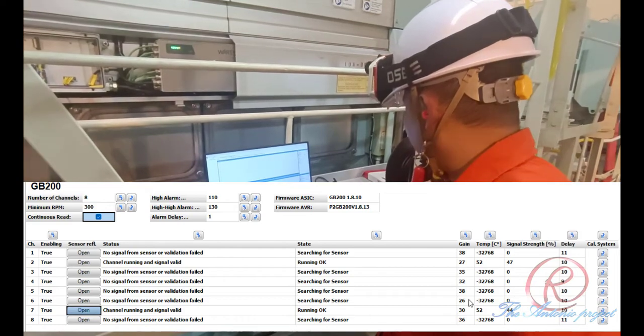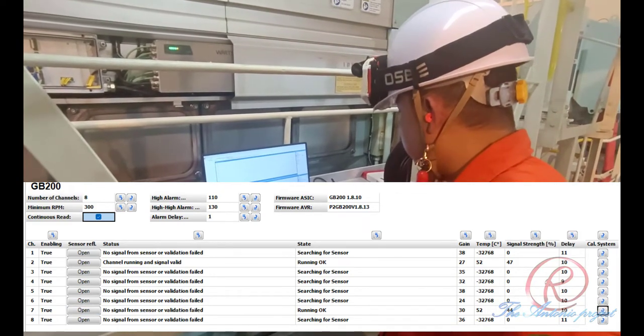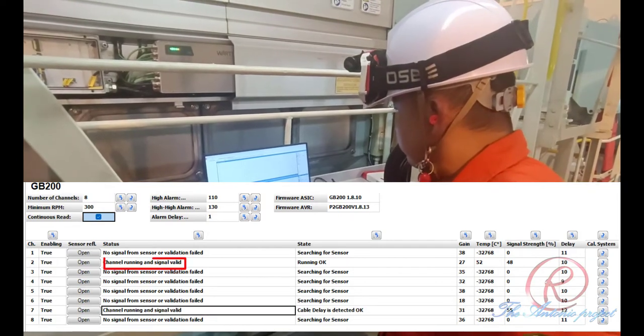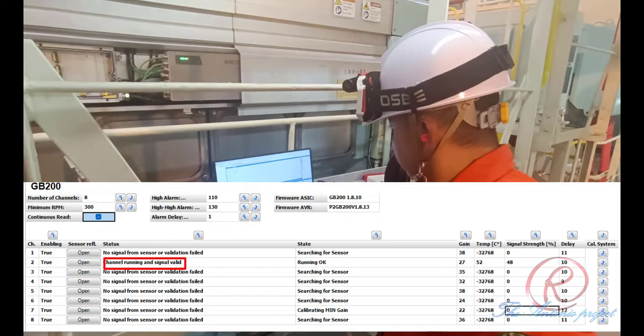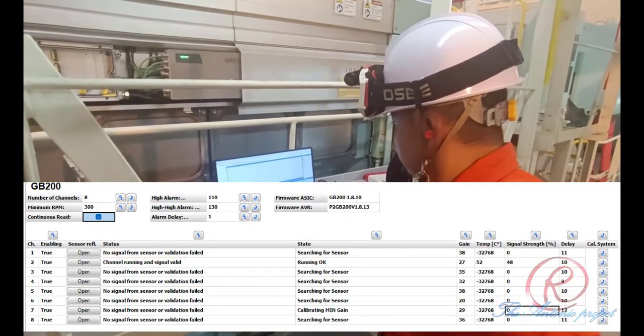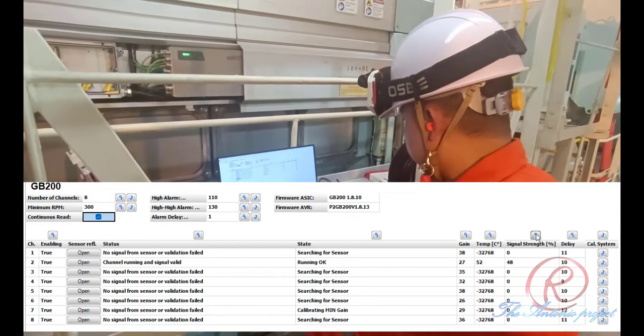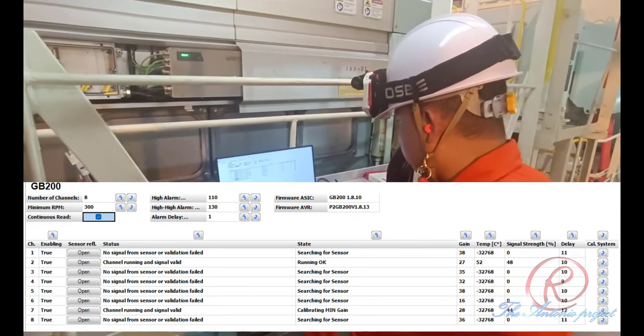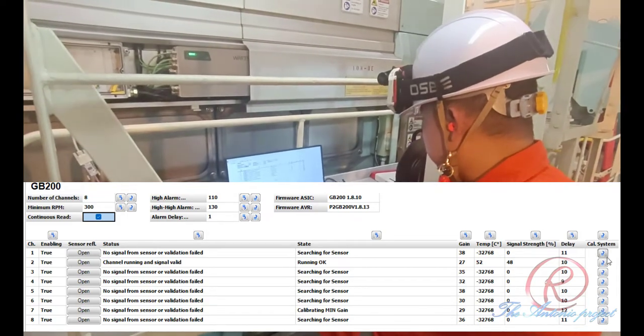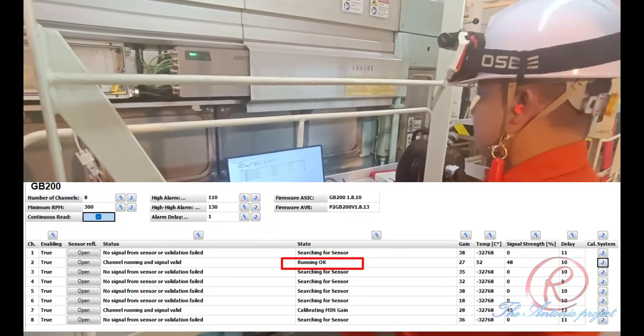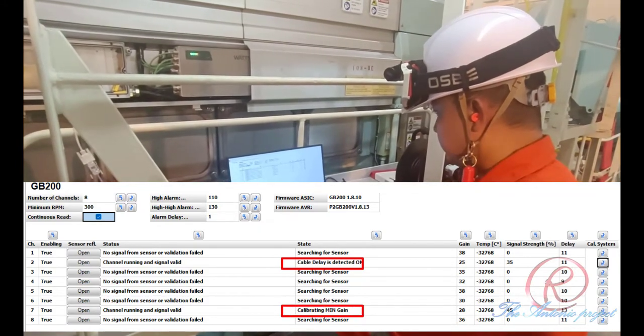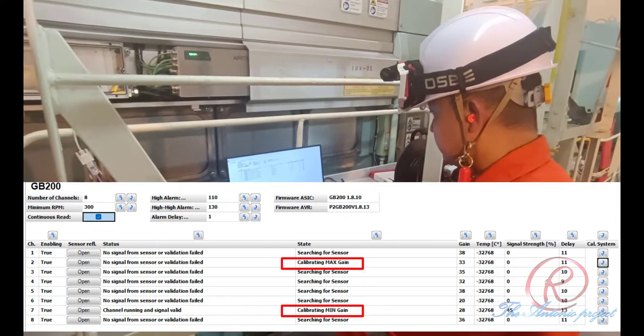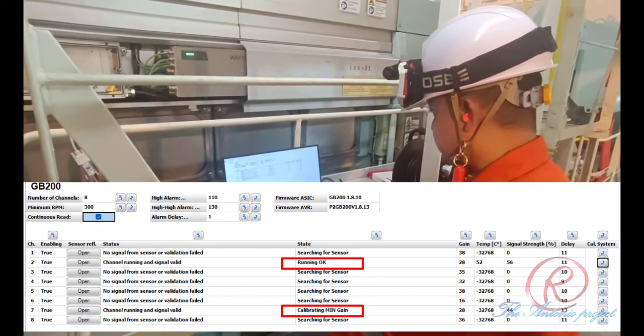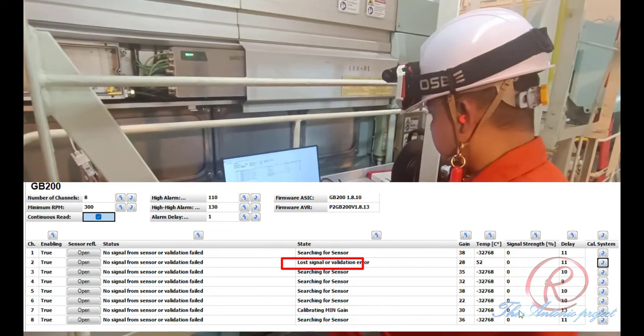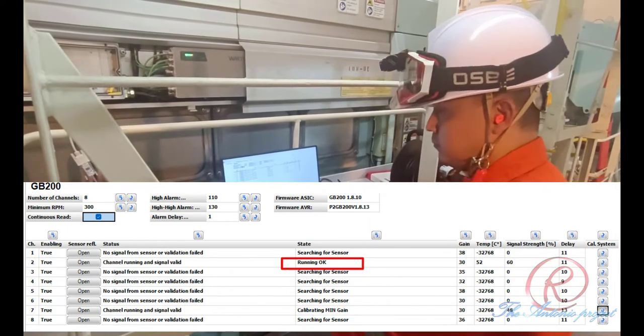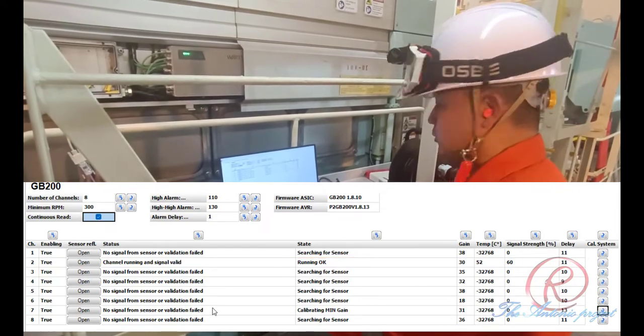When confirmed that the sensor status has changed from no signal from sensor or validation failed to channel running and signal valid, then we can carry out calibration by clicking Cal System. The state of the sensor channel will change from calibrating cable delay is detected, OK, calibrating min gain, calibrating max gain to running, OK. The cable delay will automatically update the calibrated value if continuous read is enabled. As you can see, for sensor number 7 the status remains unchanged. It is stuck in calibrating min. But for sensor number 2, the status is running normally.